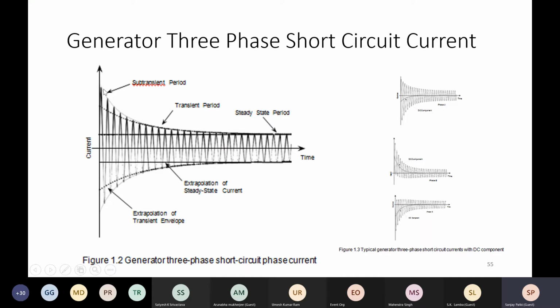Whereas the sub-transient period is the peak value, which is more than 2 times the steady state value of the fault current. So all your dynamic forces on account of electrical current, the mechanical forces, will depend on the peak current. So a transformer winding, for example, has to withstand the peak magnetic force generated due to this sub-transient current.